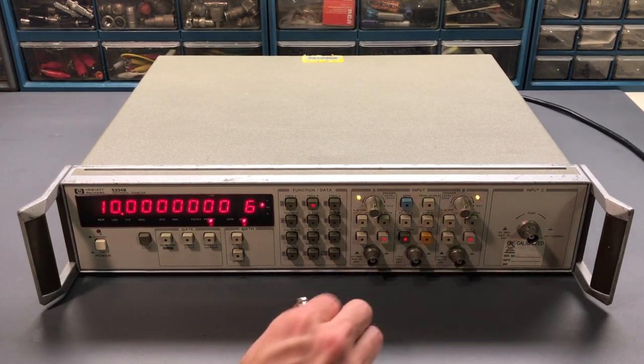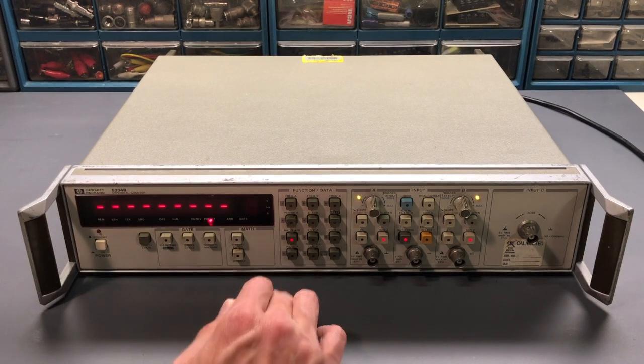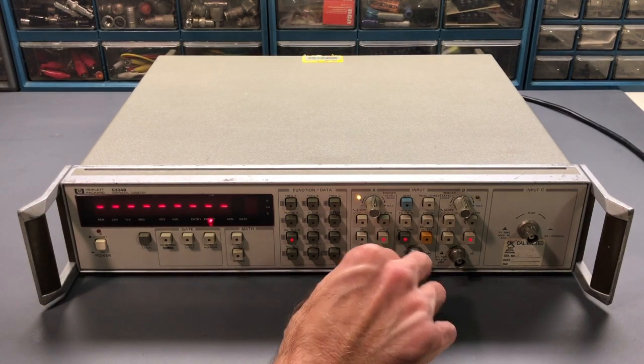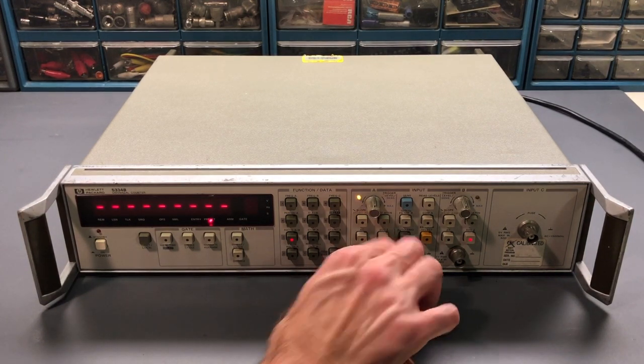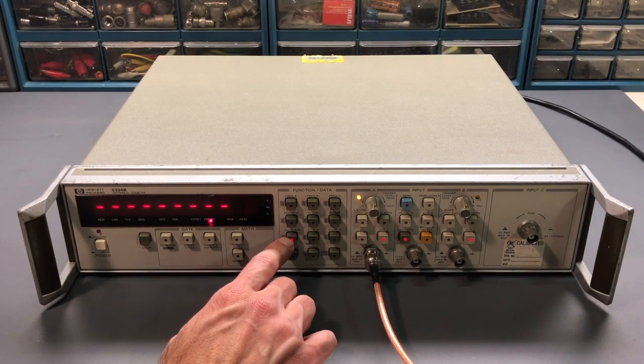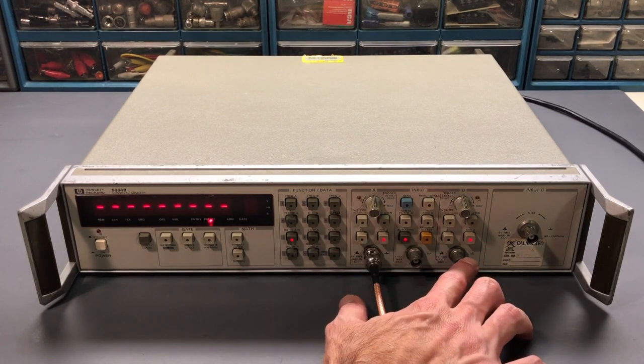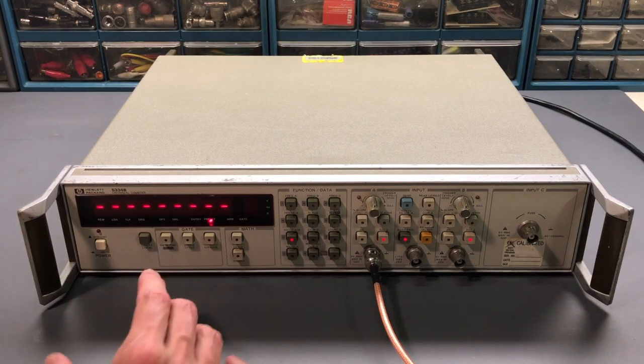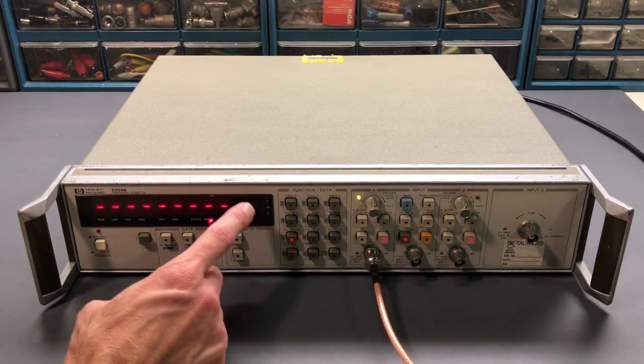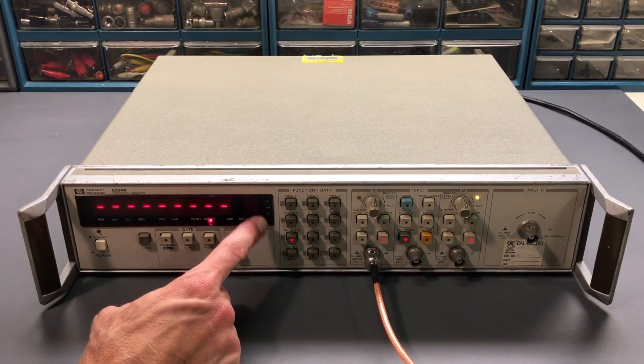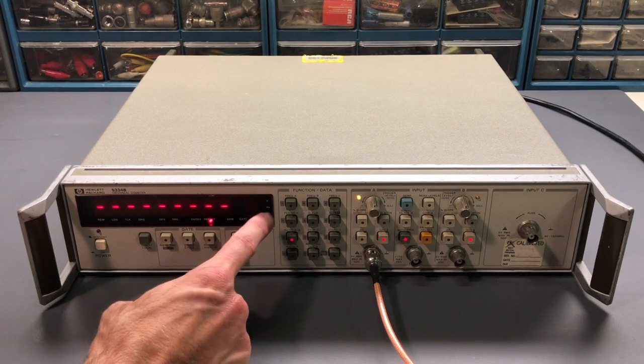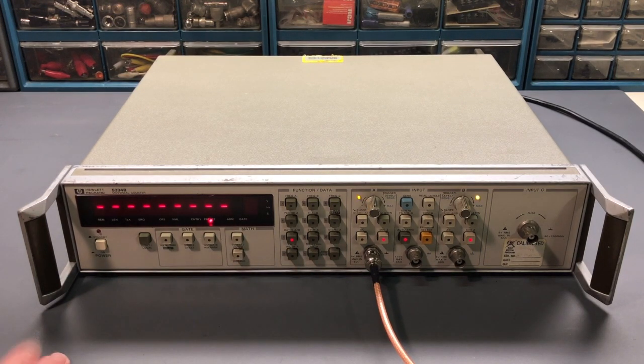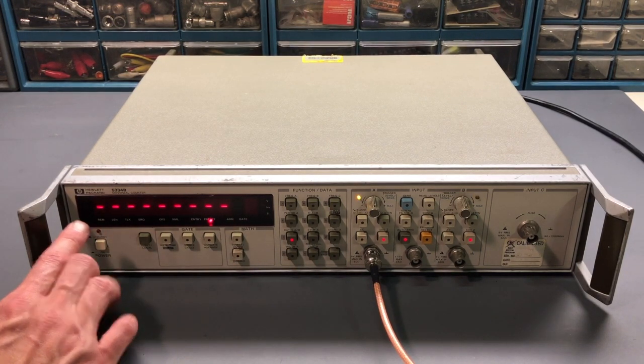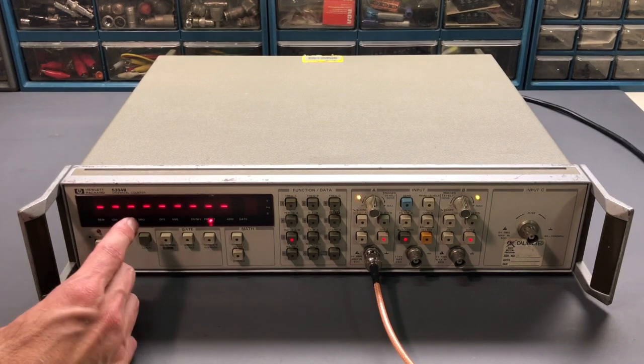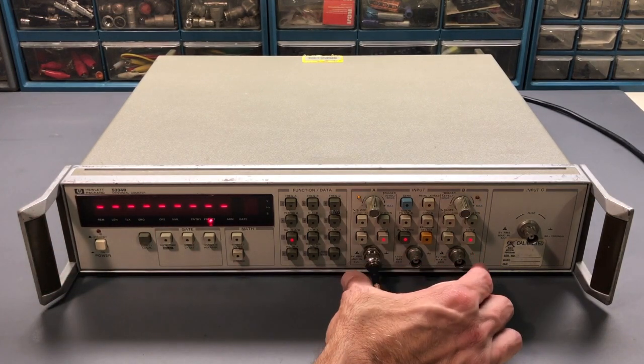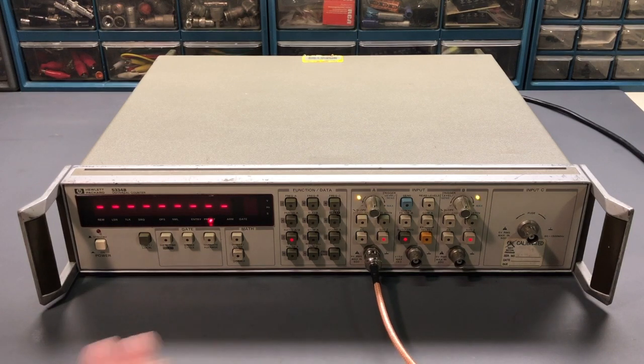Now this has a useful function for ratio measurements. I'll make this connection back here. A ratio measurement requires the A and B inputs, and it's really just a ratio between these inputs. Notice there's no voltage, hertz, or time indication now—those indicators have gone out. A ratio is just that: if it says 1, it's a 1-to-1 ratio between the two inputs, meaning they're the same.